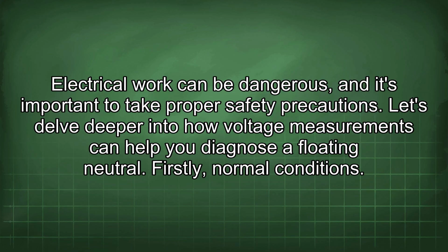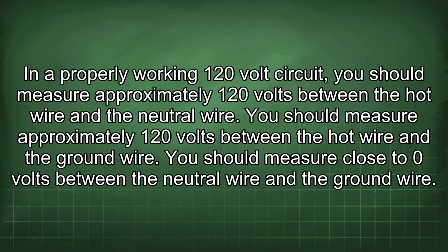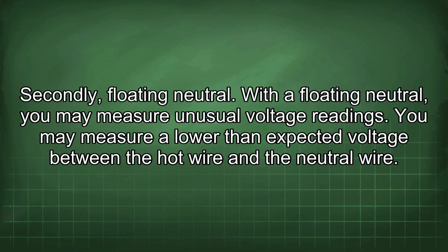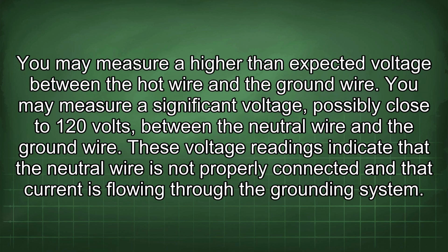Let's delve deeper into how voltage measurements can help you diagnose a floating neutral. Firstly, normal conditions. In a properly working 120 volt circuit, you should measure approximately 120 volts between the hot wire and the neutral wire. You should measure approximately 120 volts between the hot wire and the ground wire. You should measure close to 0 volts between the neutral wire and the ground wire. Secondly, floating neutral. With a floating neutral, you may measure unusual voltage readings. You may measure a lower than expected voltage between the hot wire and the neutral wire. You may measure a higher than expected voltage between the hot wire and the ground wire. You may measure a significant voltage, possibly close to 120 volts, between the neutral wire and the ground wire.